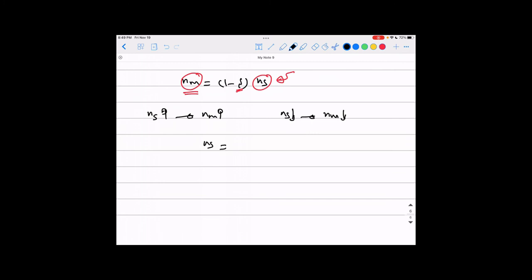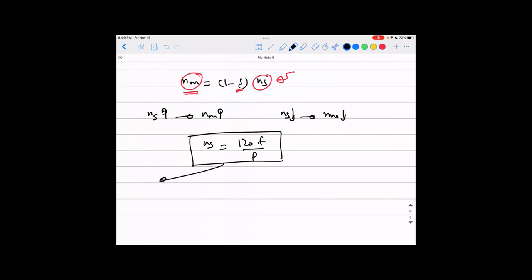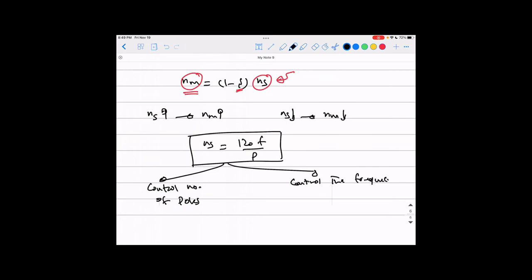How can we control the synchronous speed? Look at the equation: ns = 120f / P. You have two parameters you can control: number one, control the number of poles; or number two, control the frequency of the stator voltage.